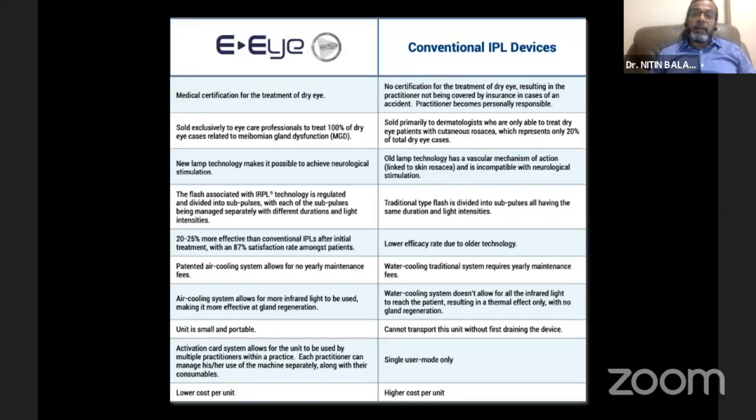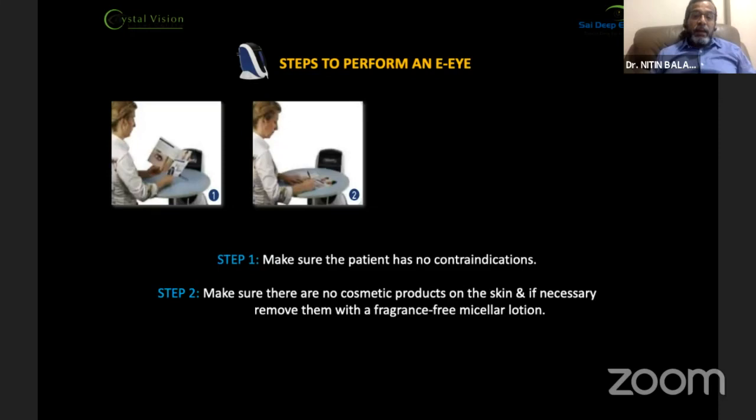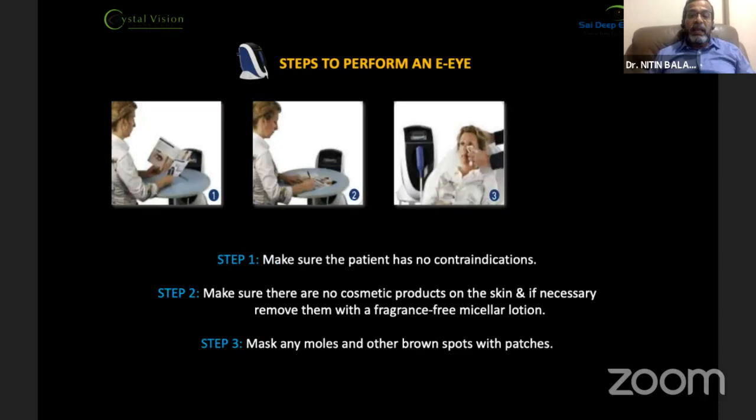The steps to perform an E-Eye begin with checking for contraindications. These include pregnant patients, patients with very dark skin, patients with skin disorders, tattoos around the eye, or permanent eye makeup. Ensure there are no cosmetic products around the eye before the procedure; if present, they should be cleaned off. All moles or dark pigmented spots in the treatment area should be covered with the patches supplied with the unit.